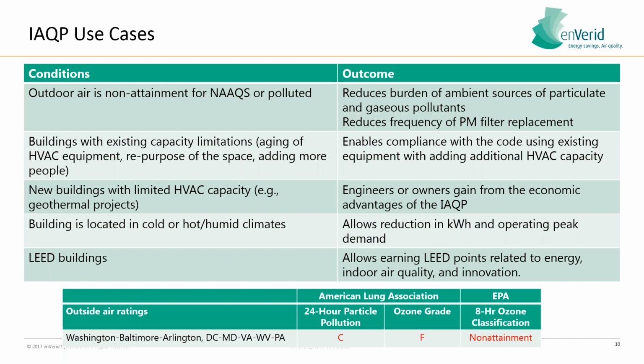Buildings in cold or hot climates are great applications because we can reduce greenhouse gases and allow for a kilowatt-hour reduction, because it costs less to heat or cool air if you're bringing in a lower volume of total air. And by removing CO2 and all these other contaminants, the EnVerid solution is uniquely able to achieve up to 16 LEED points under the EQPC 124 LEED pilot credit. We'll go deeper into that. We're also eligible to get WELL points through the WELL Building Standard.